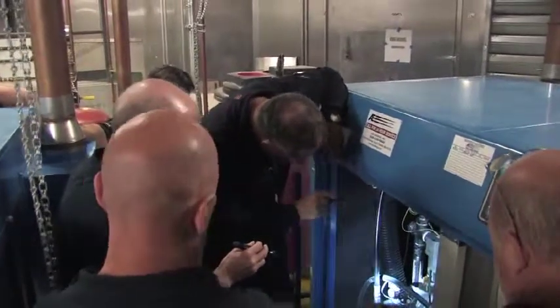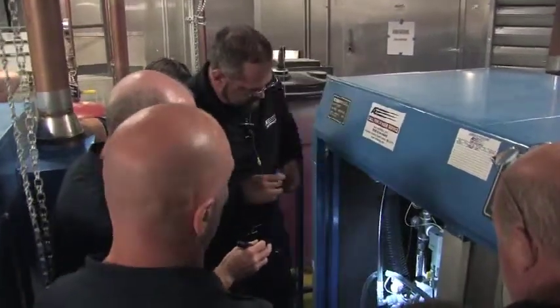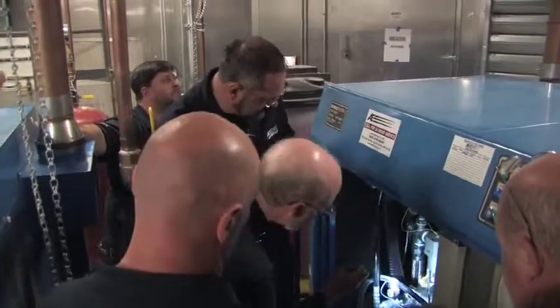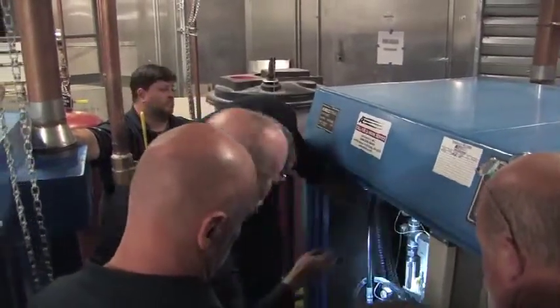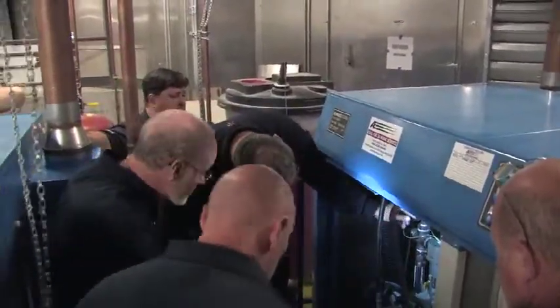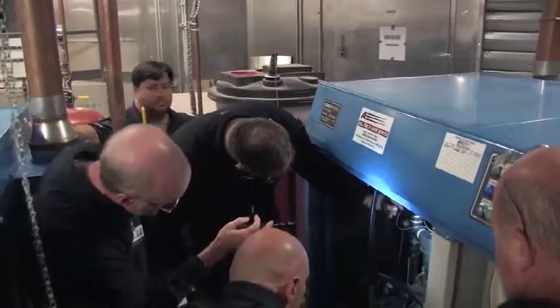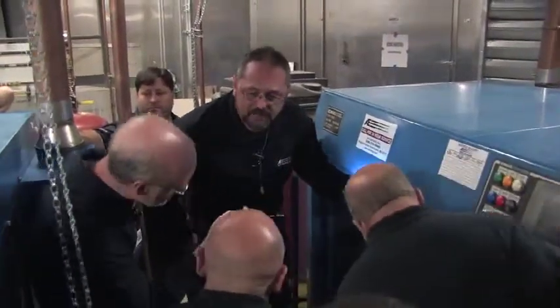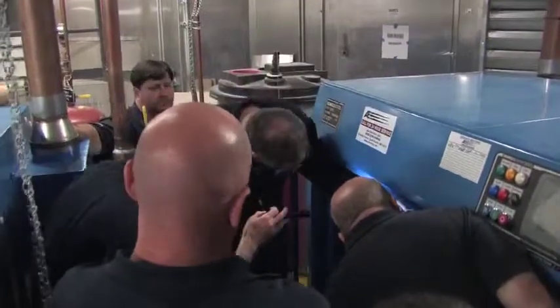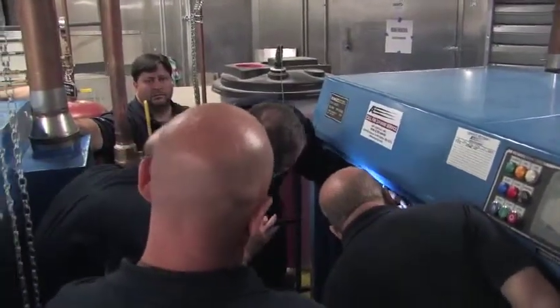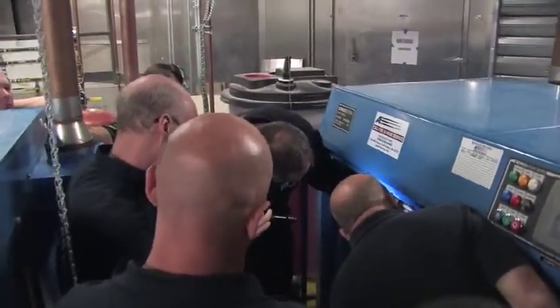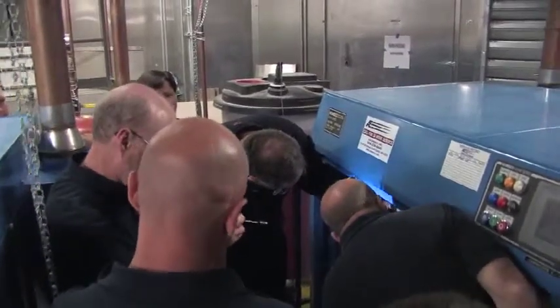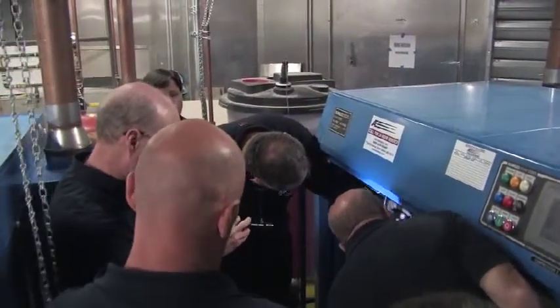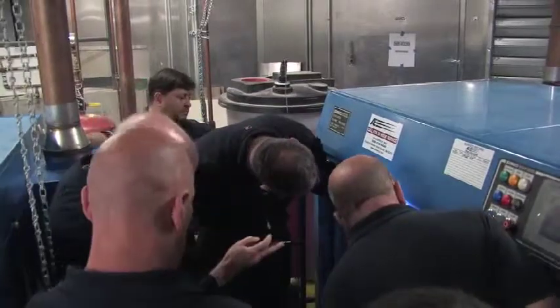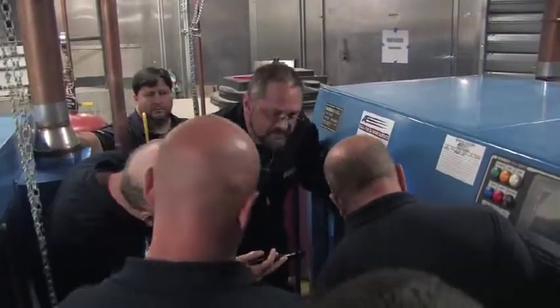So it'll come in on a pressure alarm versus that. Obviously. Okay. So again, on the back side here, some of your older machines may not have this. Oh, that's a new demister, huh? Yep. We've got a lot of people who are retrofitting these now. Very nice. I like that because that's going to keep the inside of that cabinet a lot drier. Because those demisters work real well if you don't mind picking the oil up off the floor. Yep, that's the latest style on the demisters. Goes back into the sump. Goes back down into the base of the sump and trickles.